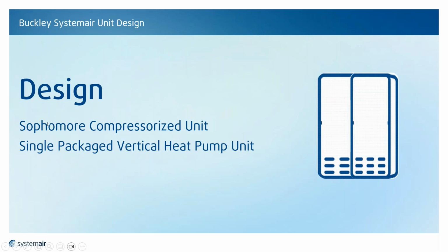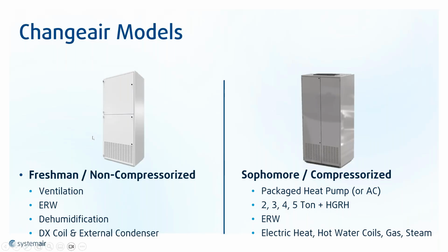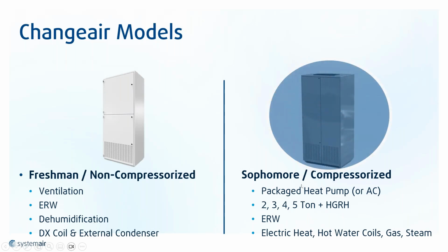Let's get into a bit more on the design of the compressorized units now. So before we were talking in general for both units, now we're just going to focus primarily on the sophomore unit. The sophomore unit can be a packaged heat pump, or you could have a packaged air conditioner, so just cooling. You have your options of 2 to 5 tons. You can have the option of hot gas reheat. Energy recovery wheel, again, optional for those who need it. Electric heat can be your supplemental if you have a heat pump or your backup. Or you could choose hot water coil as your supplemental or your backup. And again, if those become the main heat sources, if you take the packaged AC option.